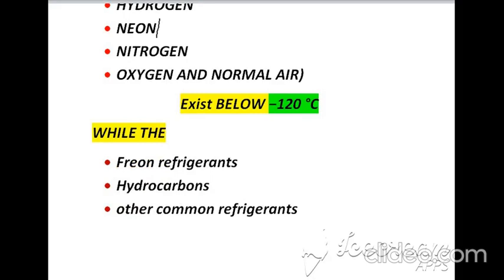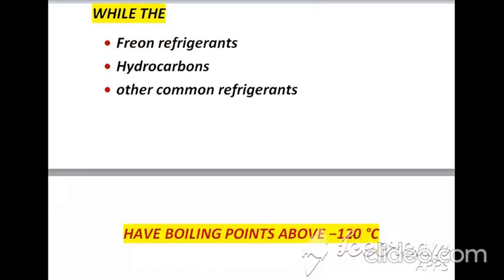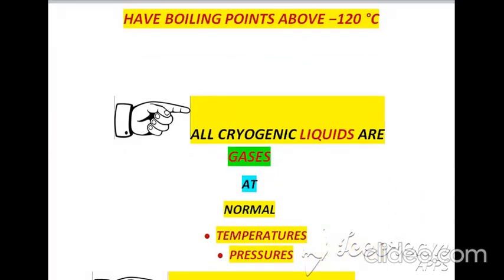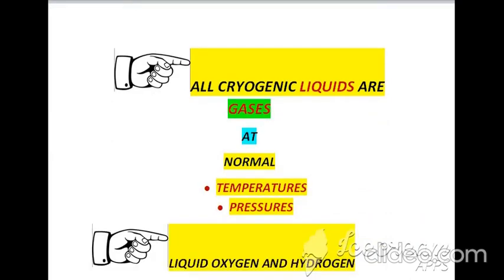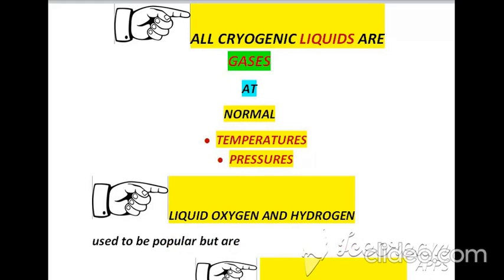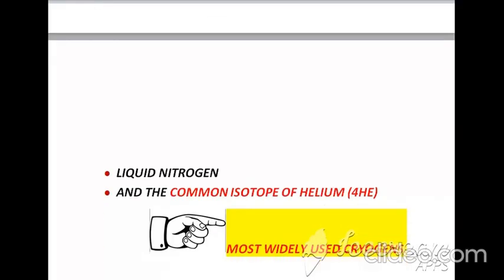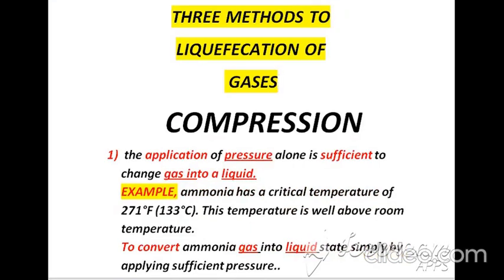Freon refrigerants, hydrocarbons, and other common refrigerants used in different equipment for refrigeration have boiling points above negative 120°C. Remember, all cryogenic liquids are gases at normal temperature and pressure. Liquid oxygen and hydrogen used to be popular but are rarely used nowadays due to potential hazards, so liquid nitrogen and the common isotopes of helium are most widely used for cryogenic purposes.